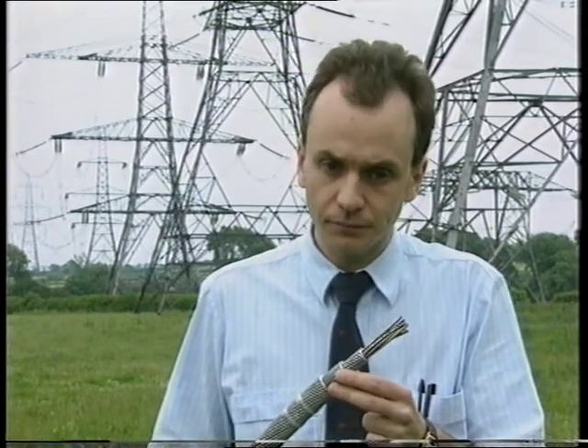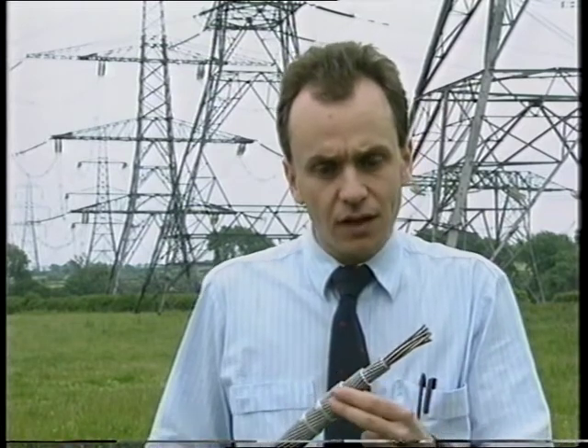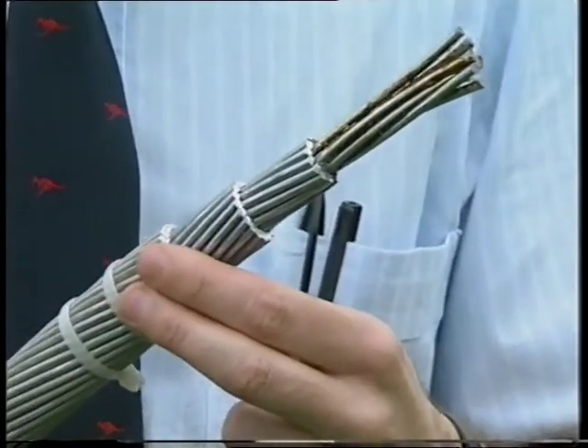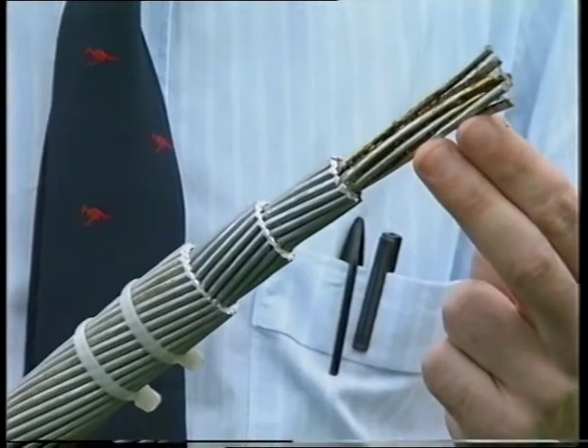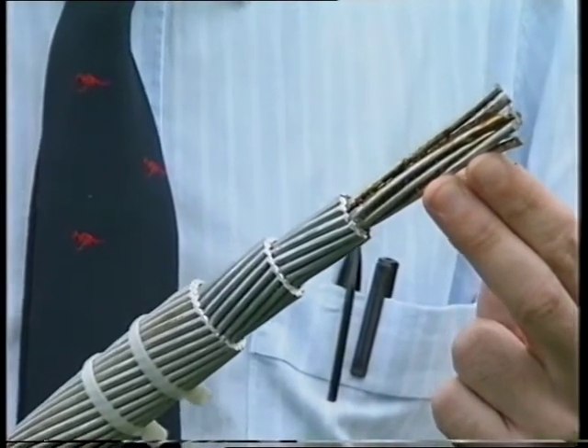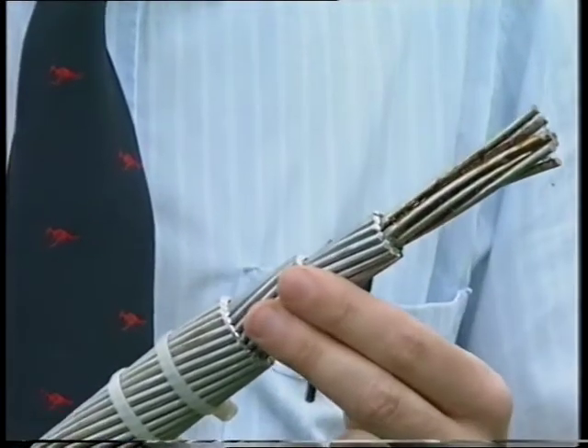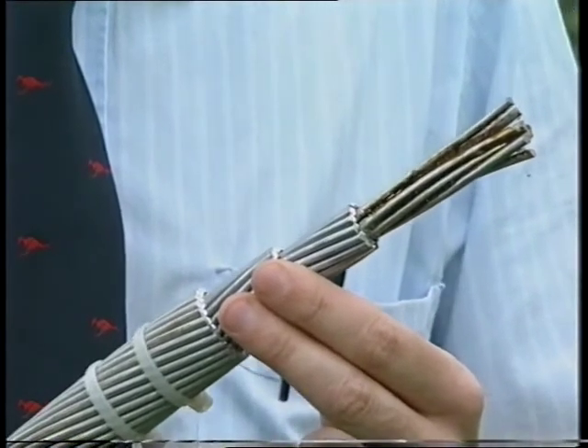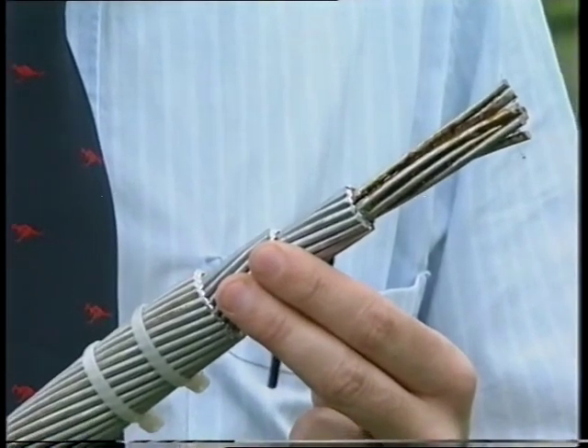The other factor we can tinker with is the cross-sectional area A. The resistance R is inversely proportional to A, so if we can make the area larger, we'll lower the resistance of the cable. But it's not as simple as that. If we clad the cable with extra aluminium, then we'll need extra steel for structural support, and that raises all sorts of issues, like the spacing of the pylon and the tension in the cable.